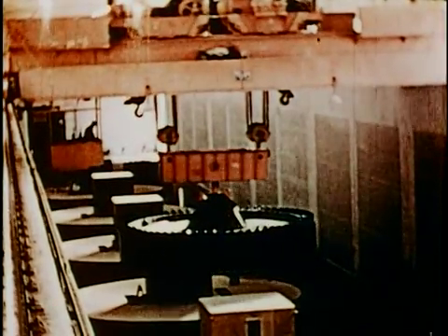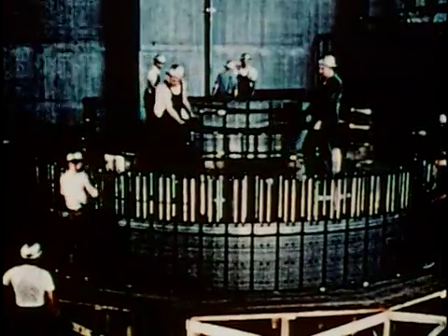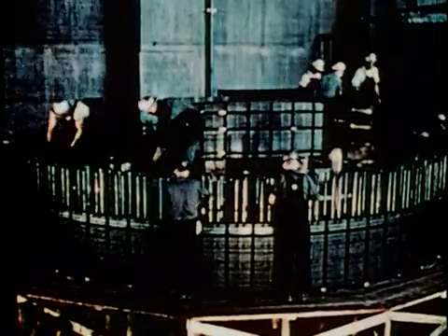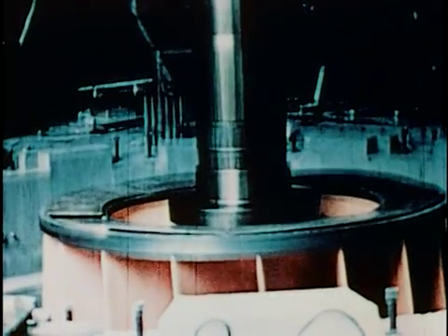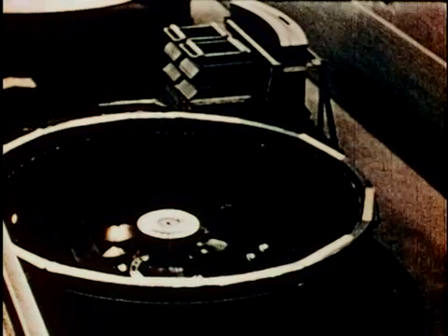The seven original generating units were supplied by General Electric, and each was designed to output 40 megawatts, or 40 million watts. The huge rotors were assembled on site. They're made of thousands of steel plates called punchings, stacked to form the rim of each of the 207-ton rotors. The punchings were carefully weighed before they were placed around the rim to ensure proper balance and prevent vibration when all 207 tons started spinning to generate voltage. The original turbines were supplied by the Newport News Shipbuilding and Dry Dock Company, each designed to produce 55,000 horsepower, using 17 buckets and 24 wicket gates to get the job done.